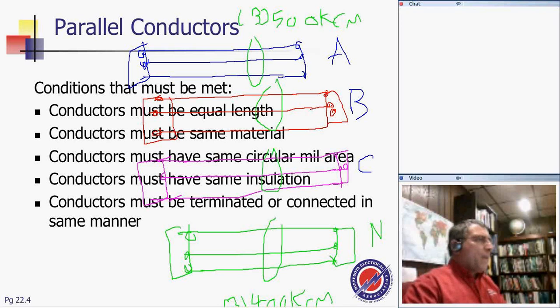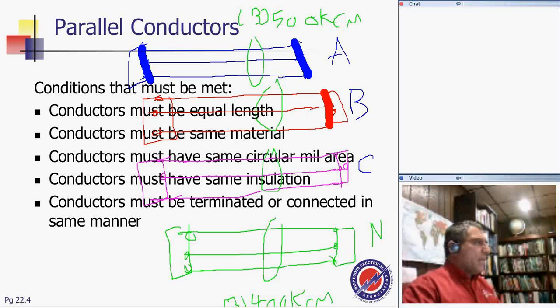Why would we parallel conductors? The challenge, guys, always comes: why would you parallel? What does paralleling conductors mean? I can't emphasize it enough, guys. When you parallel conductors, you are tying them at the end. That's basically what paralleling conductors is. For phase A, you're tying them at the end, and for phase B, as well as for phase C, you go to the end and tie them at the end. Also for the neutral, the same thing. You go and you tie these conductors at the end.